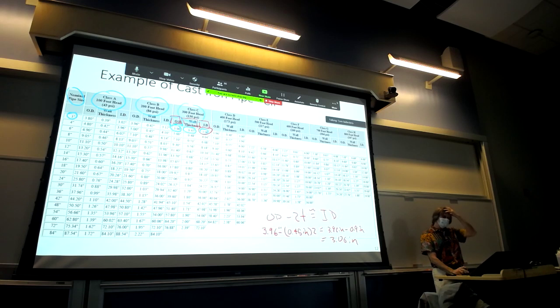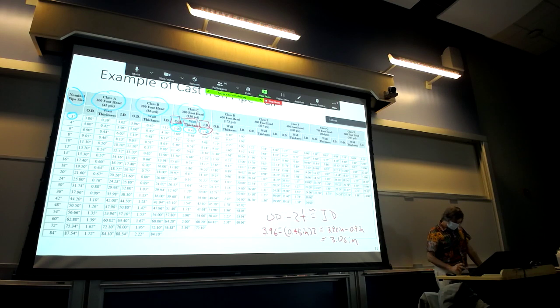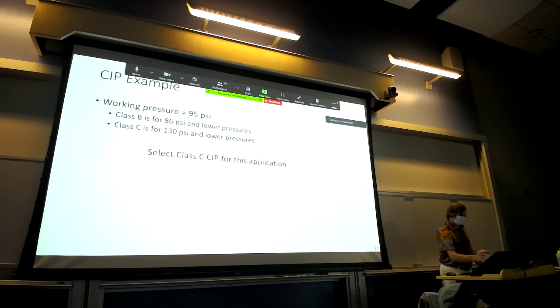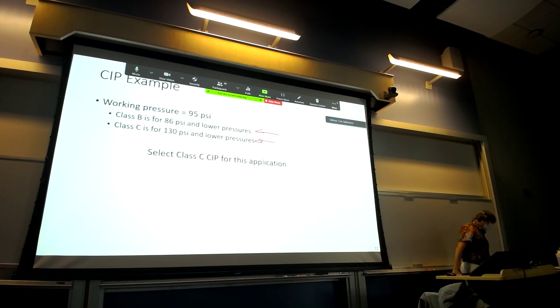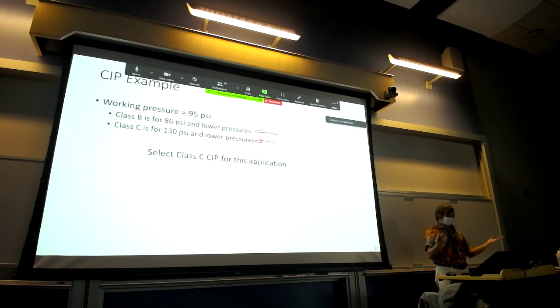Going back to the example with 95 PSI: looking at the headings on the cast iron pipe handout, class B is for pressures up to 86 PSI, and class C is for pressures up to 130 PSI. So if your working pressure is 95 PSI, you would select class C cast iron pipe.